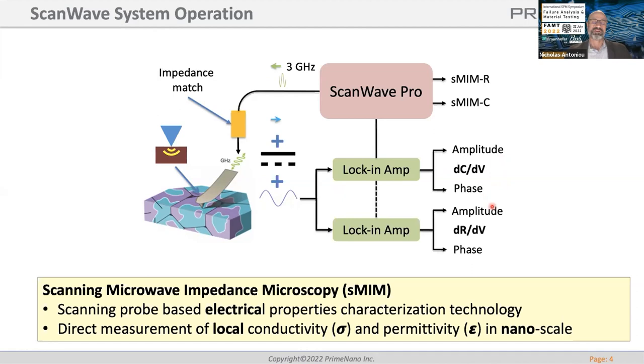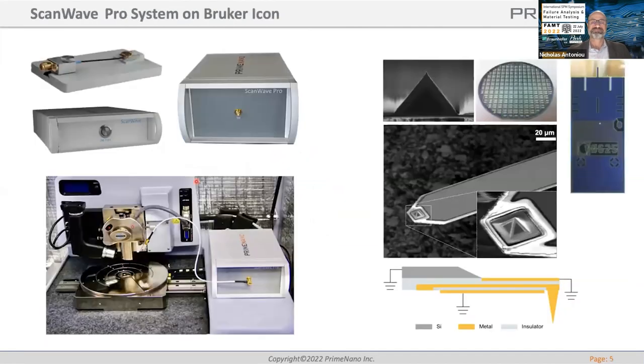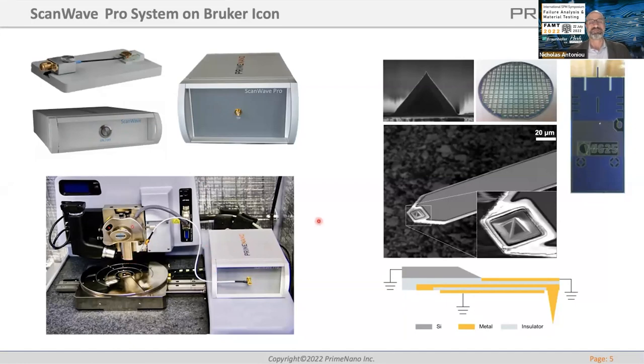You can also do dRdV, and in addition you can add a DC signal and ramp it — I'll show examples of that. These are pictures of the system. The three main components are: a probe interface module which holds the probe and provides impedance matching; an extremely low-power, low-noise power supply that powers the RF generator; and here you see it installed in our lab with the RF generator connected to the probe interface module and the cantilever on the head.